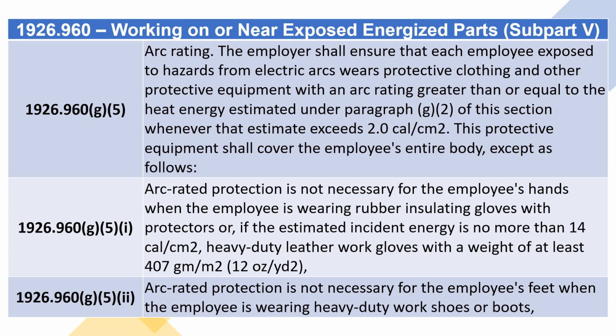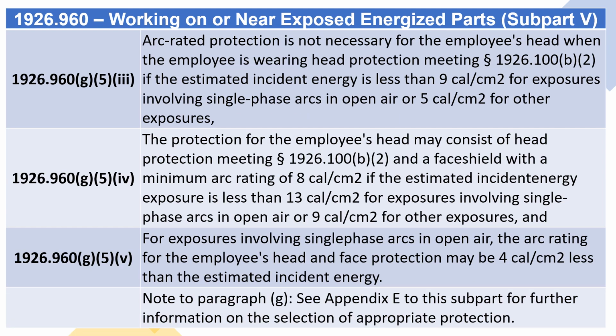Arc-rated protection is not necessary for the employee's hands when the employee is wearing rubber insulating gloves with protectors or, if the estimated incident energy is no more than 14 calories per square centimeter, heavy-duty leather work gloves with a weight of at least 407 g/m², 12 oz/yd². (g)(5)(ii) Arc-rated protection is not necessary for the employee's feet when the employee is wearing heavy-duty work shoes or boots. Arc-rated protection is not necessary for the employee's head when the employee is wearing head protection meeting section 1926.100(b)(2) if the estimated incident energy is less than 9 calories per square centimeter for exposures involving single-phase arcs in open air or 5 calories per square centimeter for other exposures.